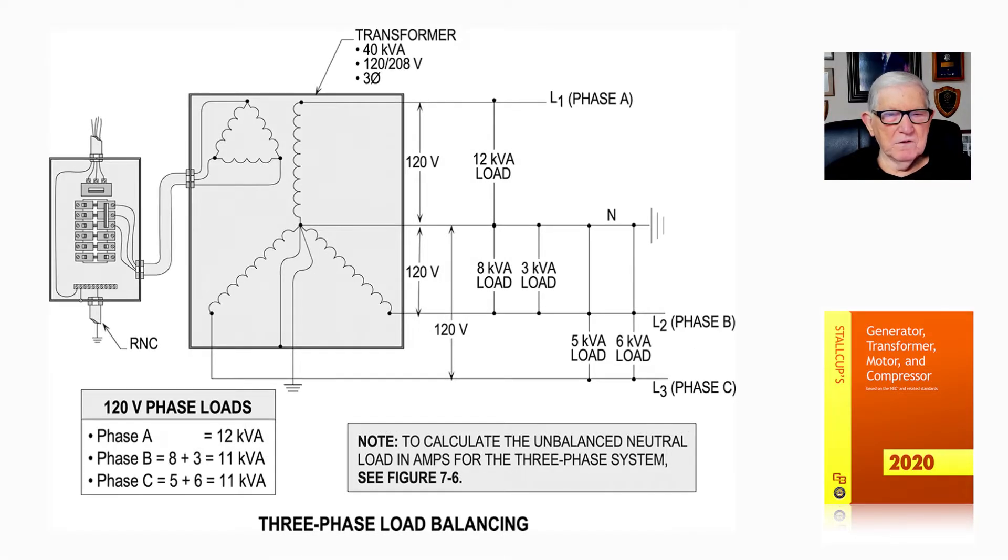Now let's take a look at Figure 7-12A and notice it's three-phase load balancing. When you review the loads, the 120-volt loads, simply looking at it in a more simple manner, phase A is 12 kVA, phase B is 8 plus 3, which is 11 kVA, and phase C is 5 plus 6, which is 11 kVA.